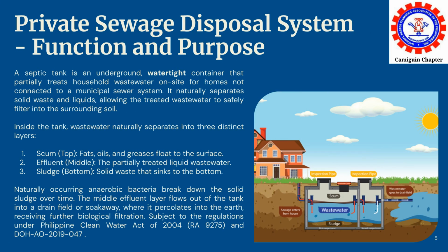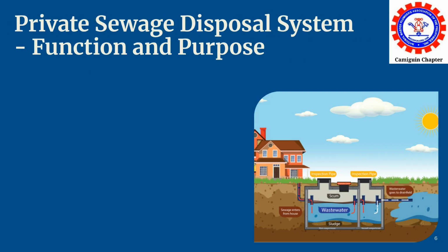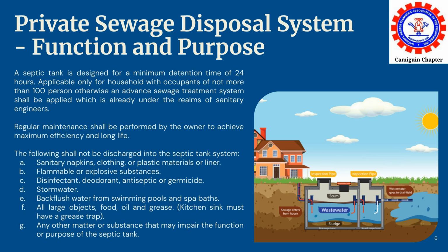A septic tank is a watertight container that partially treats household wastewater by separating it into three layers: scum, effluent, and sludge. Anaerobic bacteria break down the sludge, and the effluent flows into a drain field for further filtration. Septic tanks must provide a minimum detention time of 24 hours. Owners must perform regular maintenance.